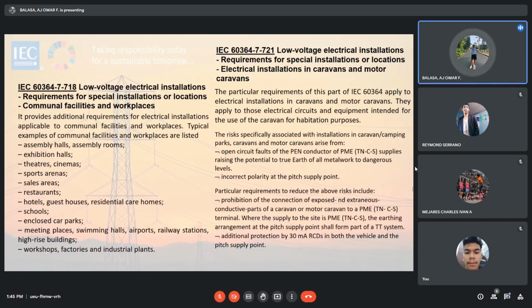Particular requirements to reduce the above risk include prohibition of the connection of exposed and extraneous conductive parts of the caravan or motor caravan to a PME TN-C-S terminal where the supply to the site is PME TN-C-S. The earthing arrangement at the pitch supply point shall form part of the TT system. Additional protection by 30 mA RCDs in both the vehicle and the pitch point.